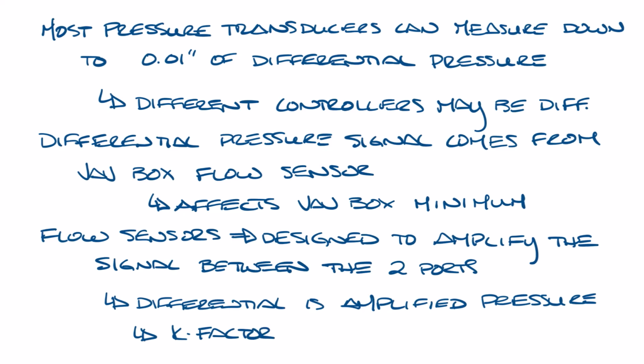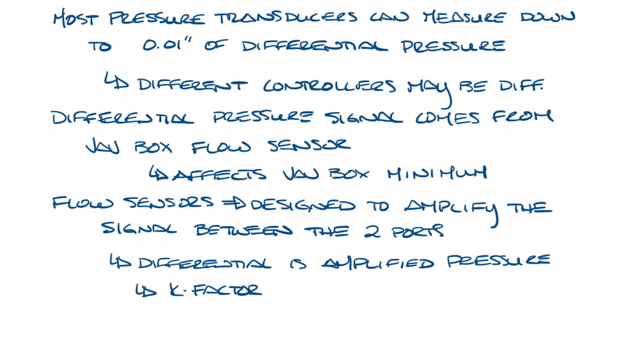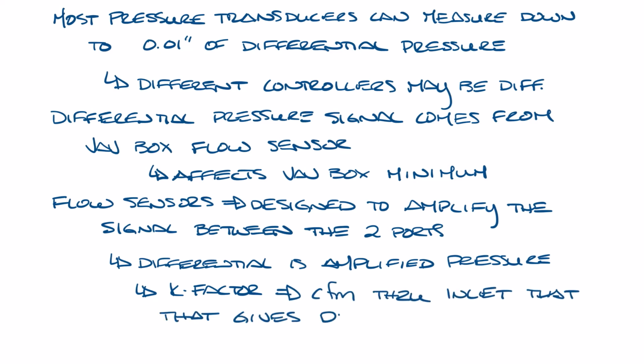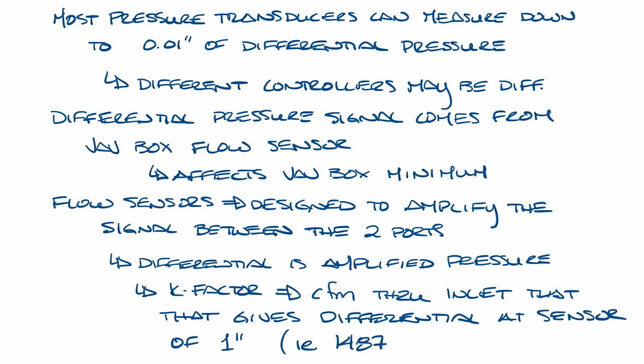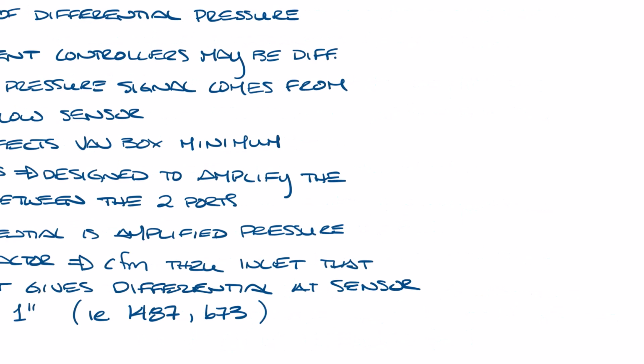Every flow sensor has a K factor. The K factor is the CFM through an inlet that gives a differential pressure across the flow sensor equal to 1 inch. And you'll see it written as a number like 1487 or 673. Let's slide this over one more time.